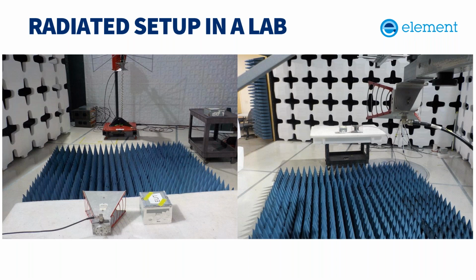So here you can see a basic setup for the radiated method. On the left, you've got the EUT communicating with a companion device on the top right, and then a level setting antenna on the bench next to the EUT. The right photo shows the interfering signal coming from an antenna radiating onto the EUT. The companion device is out of the direct beam of the antenna to try to limit interference with it. Transmit power for the EUT should be reasonable worst case, so you don't want it maxed out, but you also don't want it on noise floor.